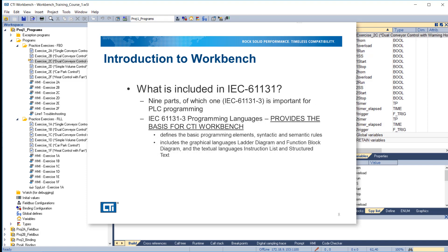What is included in IEC 61131? It has nine parts, of which one — IEC 61131-3 — is important for PLC programming. IEC 61131-3 covers programming languages and provides the basis for CTI Workbench. It defines the basic programming elements, syntactic and semantic rules, and includes the graphical languages ladder diagram and function block diagram, and the textual languages instruction list and structured text.